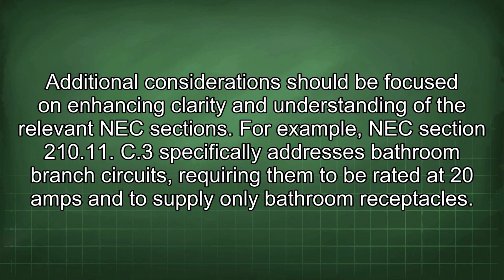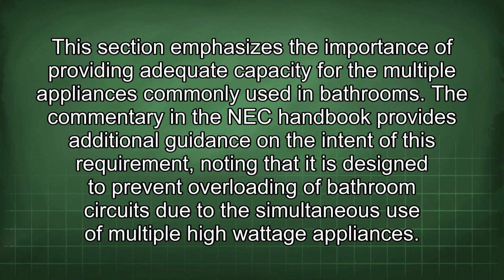Additional considerations should be focused on enhancing clarity and understanding of the relevant NEC sections. For example, NEC section 210.11(C)(3) specifically addresses bathroom branch circuits, requiring them to be rated at 20 amps and to supply only bathroom receptacles. This section emphasizes the importance of providing adequate capacity for the multiple appliances commonly used in bathrooms. The commentary in the NEC handbook provides additional guidance on the intent of this requirement, noting that it is designed to prevent overloading of bathroom circuits due to the simultaneous use of multiple high-wattage appliances.